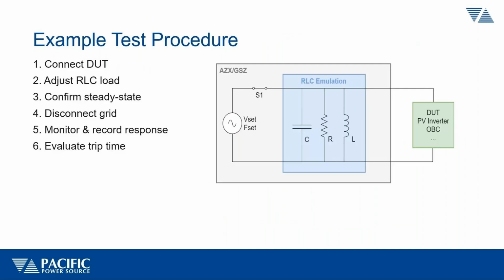The example, of course, of this test process is to run the setup with the grid simulator connected, set the RLC for the correct load so it is in balance, and then, once everything is running in a steady state condition, perform the grid disconnect. It can be done by a physical switch, or if it's a programmable grid simulator, it can be done by programming the voltage down to zero to simulate a loss of grid, and then monitor using measurement equipment, typically a scope or a power analyzer or something of that nature that can determine time domain information of the voltage and the current, and monitor the time that it takes for the DER, the DUT, to disconnect or disengage. And that trip time has to meet the test requirements. So that's the sequence of events, and very often you'll have to do this under different load conditions.